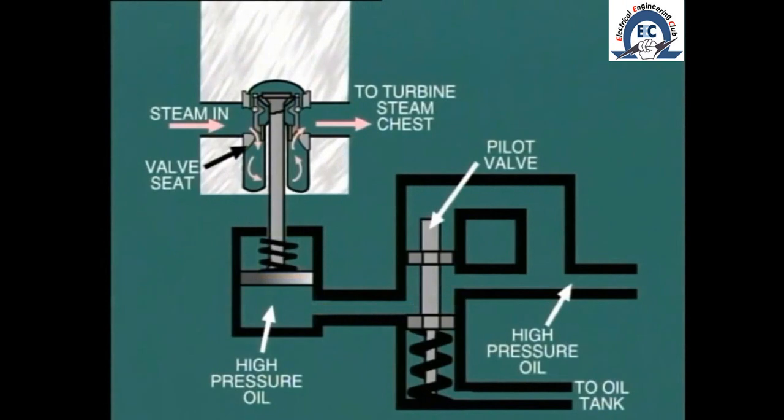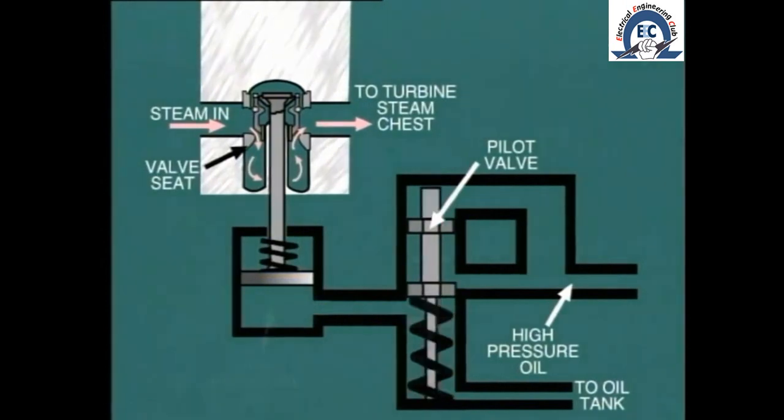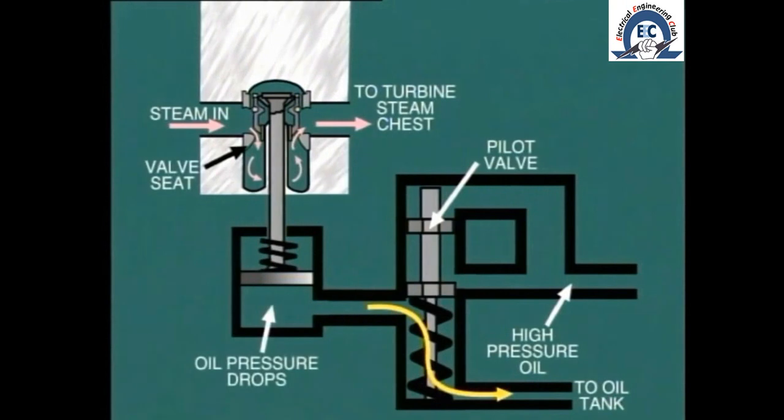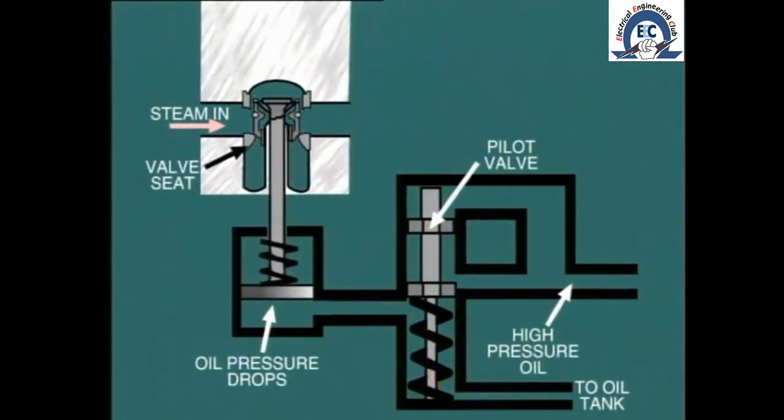In order to close the stop valve, the pilot valve must be moved to the trip position, thereby allowing the high-pressure oil to drain back to the oil tank. As a result of the sudden decrease in oil pressure below the piston, the compression spring slams the valve closed.